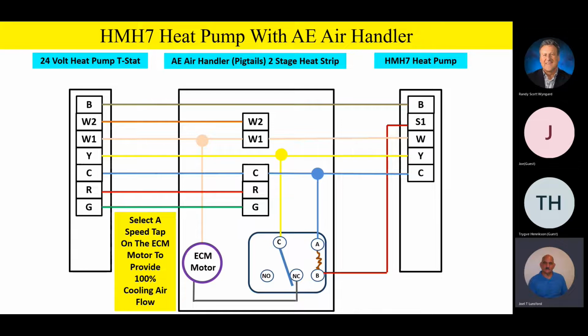We always want to make sure our cooling airflow at 100% is 400 CFM per ton of cooling. So if we have a 2-ton unit outside, it'll be 800 CFM. If it's a 3-ton unit outside, it'll be 1200 CFM, and so on. So the normally closed contact on the relay is going to energize the ECM motor on the 100% cooling airflow speed tap. Any questions or comments on that? Everybody good? No, we're good, Joel.